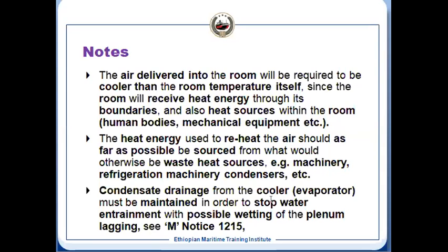And then another thing is the condensate drain. In the cooler, the coil, that is the evaporator coil in the air conditioning system, at the bottom there is a drain that always has to be clear. Otherwise, if that water remains there, it can act as a humidifier.